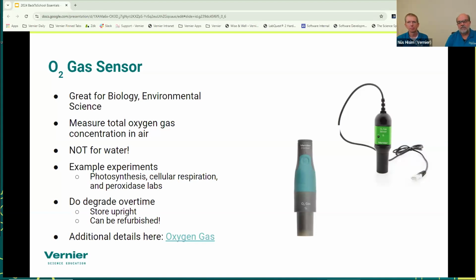The other thing to be aware of, the oxygen sensor needs to be stored vertically. It doesn't hurt it to lay it on its side, but you'll get bad data for a while. There's a gel in the sensing element, and that gel needs to be lined up vertically. So if that sensor is laying on its side over the summer, or even when you get them shipped from us, make sure that you keep them in a vertical axis, at least for an hour or two before class, so that it gives that thing a chance to level out.